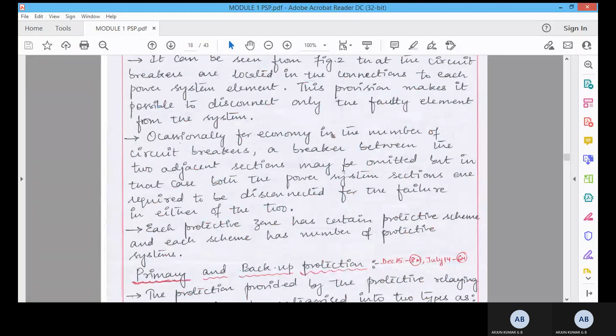Then the next one is primary and backup protection. The protection provided by the protective relay equipment can be categorized into two types: one is the primary protection, and the second is the backup protection. The primary protection is the first line of defense, and it is responsible for protecting all the power system equipment from all types of faults. The backup protection comes into play only when the primary protection fails. Backup is nothing but auxiliary protection. So any failure in the primary protection, then the backup comes into the picture.